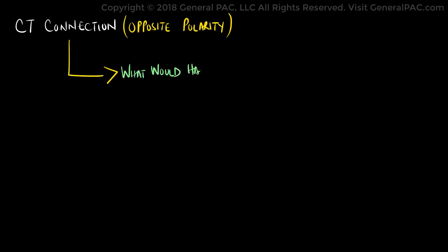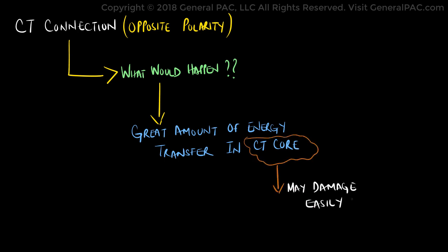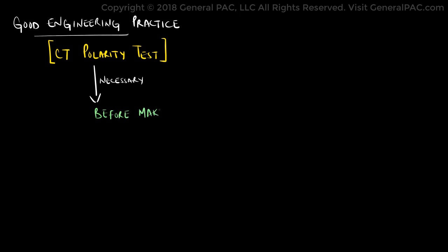But what would happen if we were to connect a CT in the opposite polarity to any equipment? Well, it would cause great amounts of energy being transferred inside the transformer core, which could potentially damage the current transformer itself. So, a good engineering practice is to always test a current transformer's polarity before performing external connections.